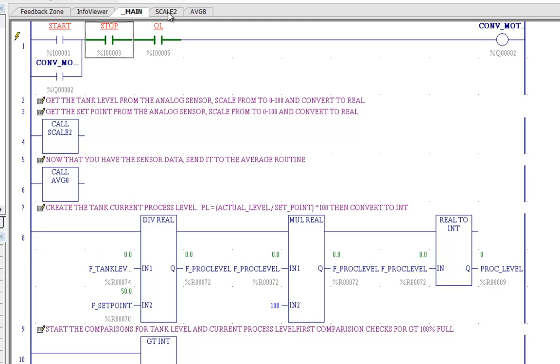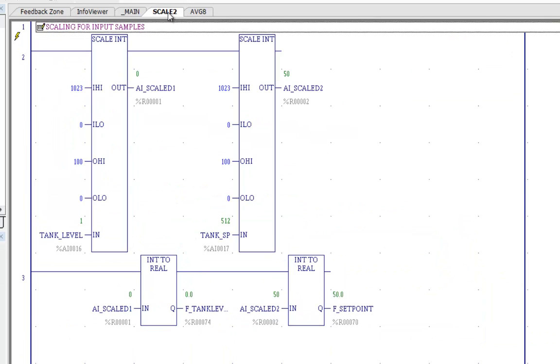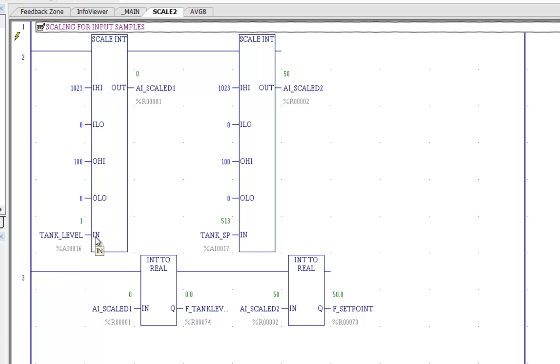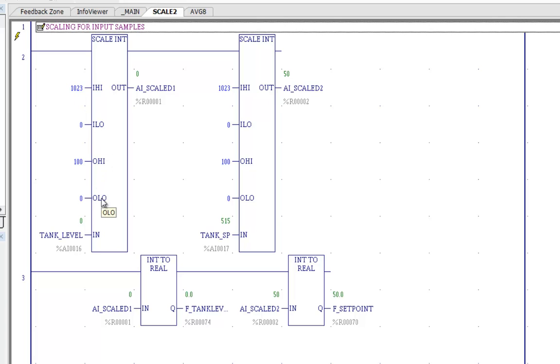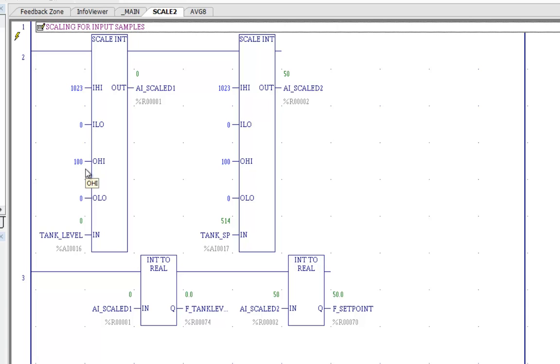So let's go back and look at scale2 and what it does it goes out and reads the analog input which is tank level. That's our input and our input low has a range of 0 and the input has a high value of 1023. And our output will then range from 0 to 100 so it will do the scaling necessary to fit everything within a 0 to 100 with our 0 to 1023 inputs. So let's take a look and see how that works.